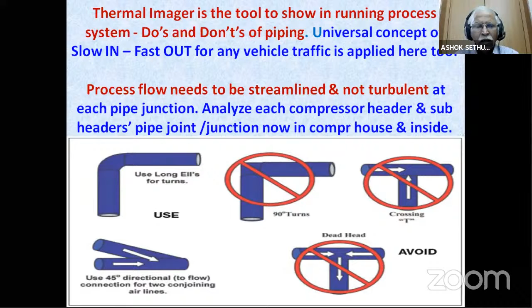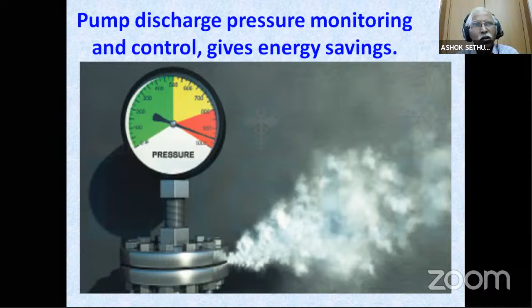For a given pump, one factor is the NPSH, and what is the optimum delivery pressure to be maintained. The optimum suction pressure and optimum delivery pressure will decide pump energy conservation in a big way. Measure your pumps in the college or in your house. What is the nameplate pressure, and what is the delivery pressure actually happening in your pipe?